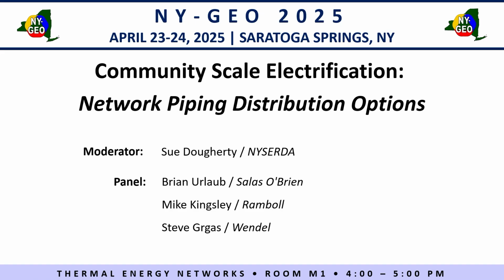What did you have for a number per square foot for cost for that upgrade? I can get you that number. I don't have it offhand, but the way the building was laid out, the mechanical rooms had the steam preheat coils all in one location, so it was pretty straightforward. All we had to do was run risers up to the mechanical rooms. The other terminal devices were, for the most part, hot water. So it's not going to be the $150 per square foot that you're seeing. There are some buildings where they're all steam and there's nothing you can do. You have to rerun new piping, and you definitely don't want to reuse the steam piping.